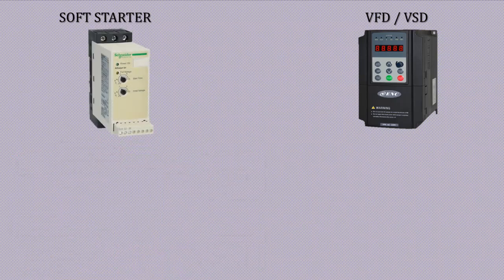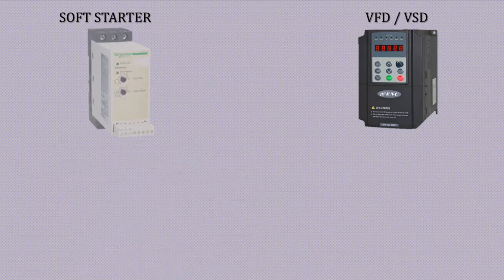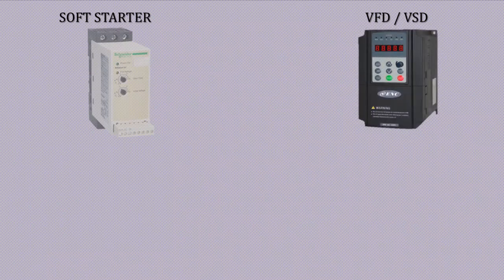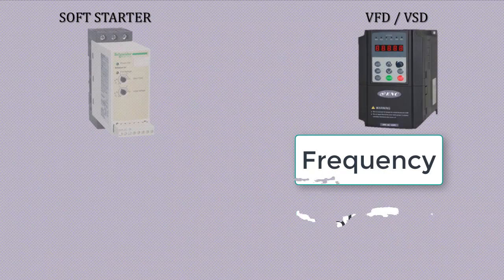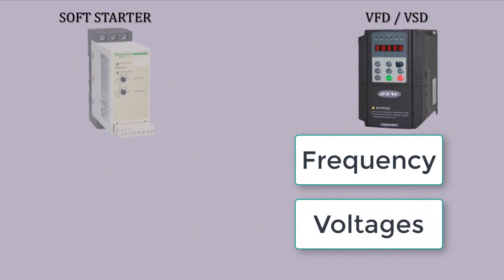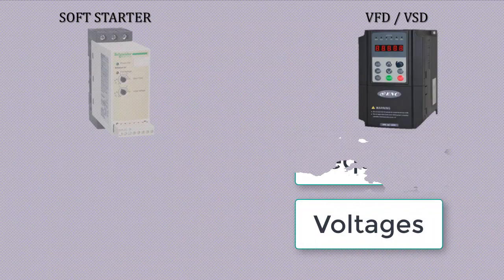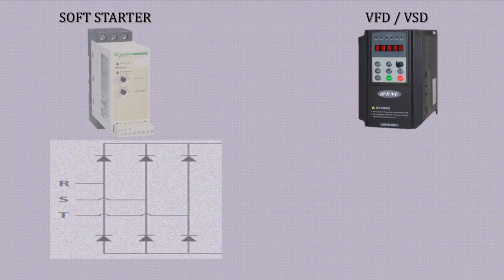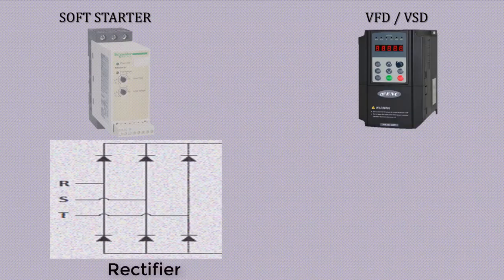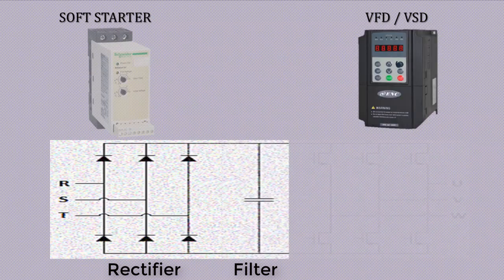Now come to variable speed drive. A variable frequency drive VFD is an electronic device that controls the speed and torque of an electric motor by adjusting both the frequency and voltage of its power supply. VFD converts three phase AC input to DC through the rectifier section, filters it through DC bus circuit, and then inverts this DC to AC supply with required voltages and frequency.